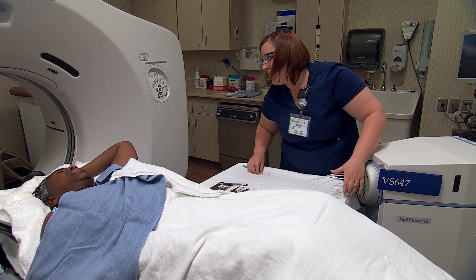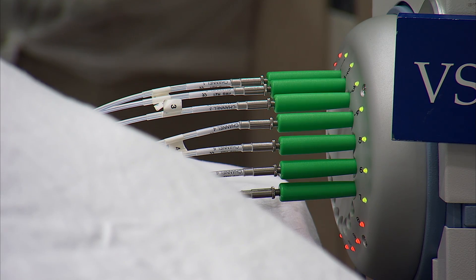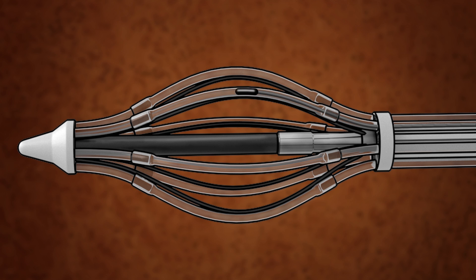the brachytherapy begins using a computer-controlled robotic machine, which manipulates a single radioactive seed smaller than a grain of rice within the implanted catheter. The radioactive seed travels through the cable into the patient and into the catheter, stopping at different locations that are programmed for different amounts of time — that shapes the radiation dose.